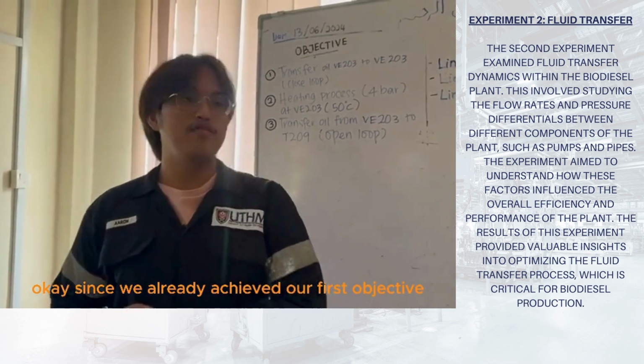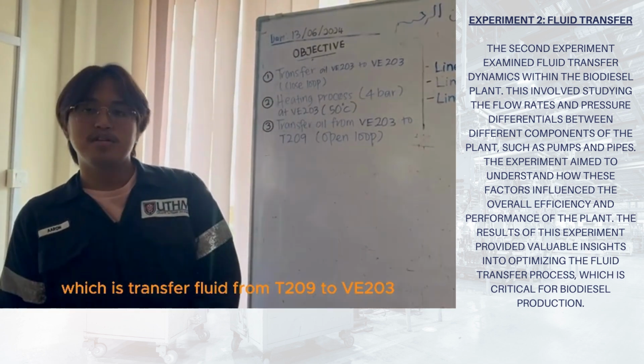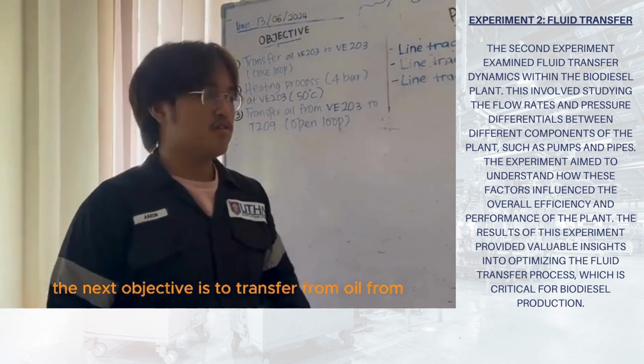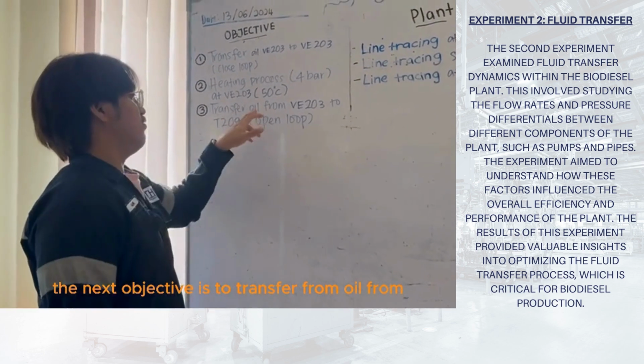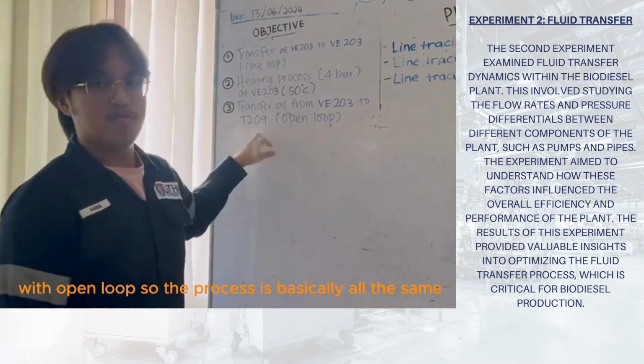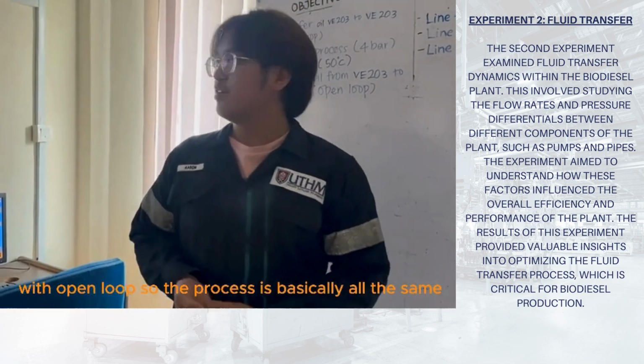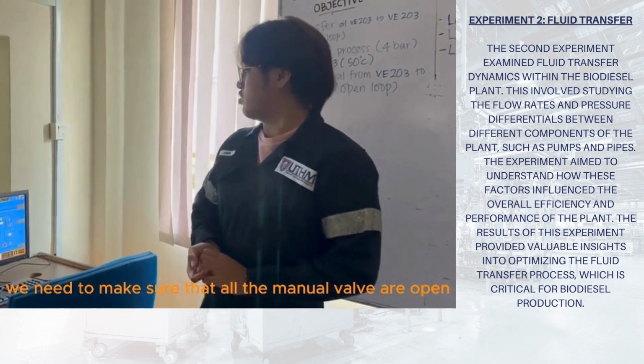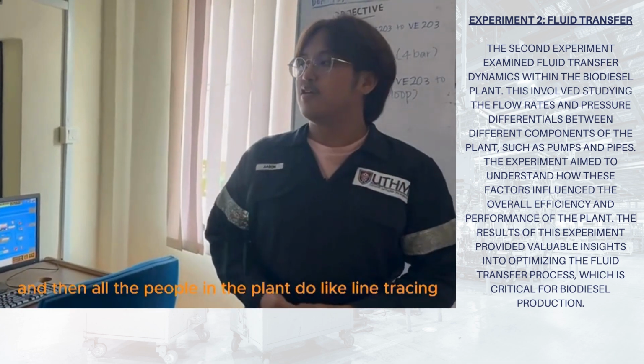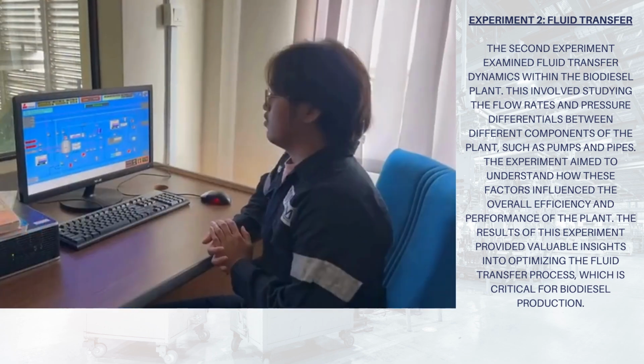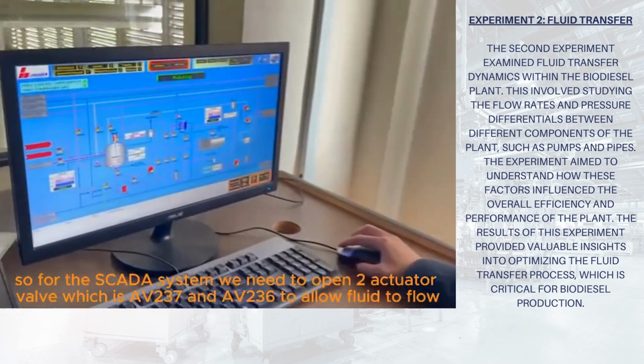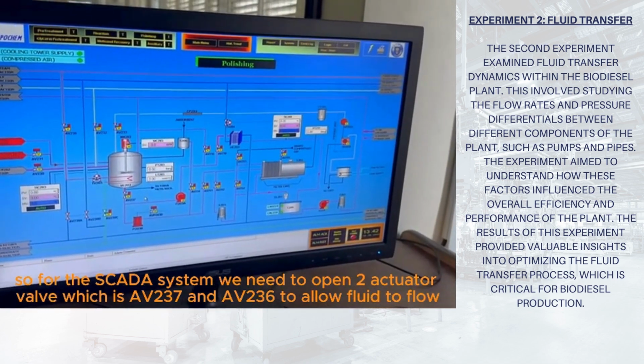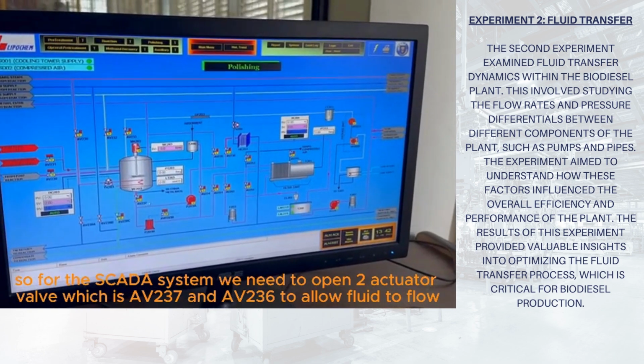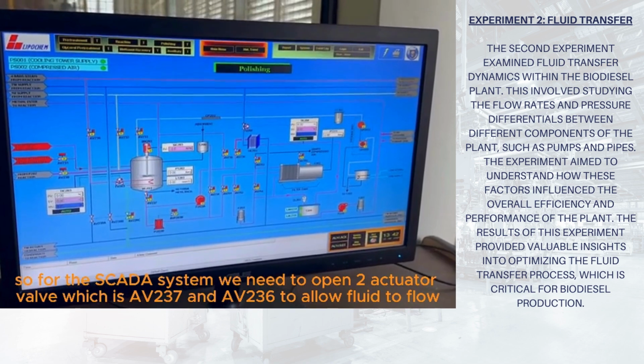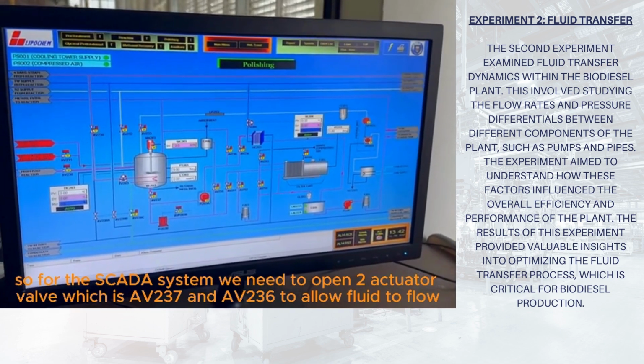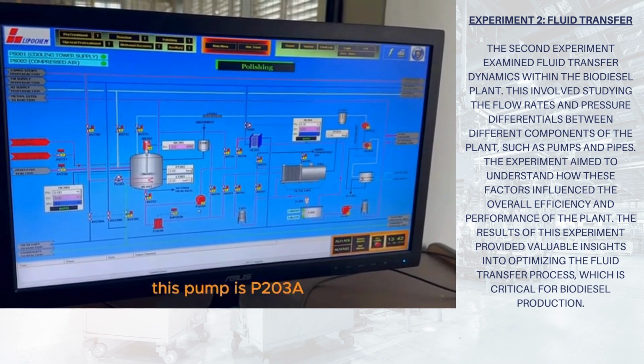Okay, since we already achieved our first objective, which is to transfer fluid from T209 to VE203, the next objective is to transfer oil from VE203 to tank T209 with open loop. The process is basically the same. We just make sure that all the manual valves are open, and all the people in the plant do line tracing and everything. For the SCADA system, we need to open two actuator valves, AV237 and AV236, to allow the fluid to flow. Then we need to make sure the pump is open as well. This pump is P203A.